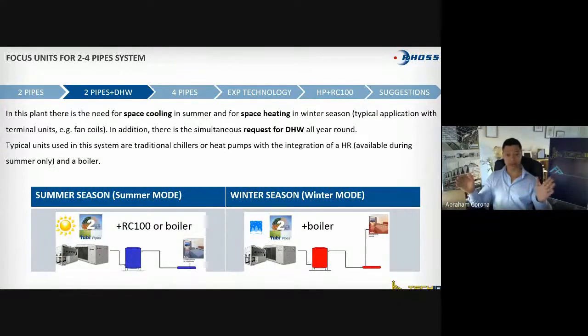Okay, starting from the beginning, let's keep it simple. It is an air-cooled version. So we have 2 pipes to be connected in and out to the primary circuit. Could be 12 to 7 if you're cooling, 45 to 55 if you're heating, like a heat pump. And now I have a heat recovery. So that means I need to connect 2 pipes that are producing hot water. Should I need this to call 4-pipe? This is what is called 4-pipe. And the answer short to that is no. This is not what it is. It's still being a 2-pipe system with a heat recovery.